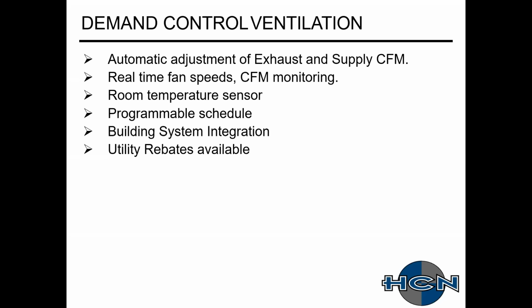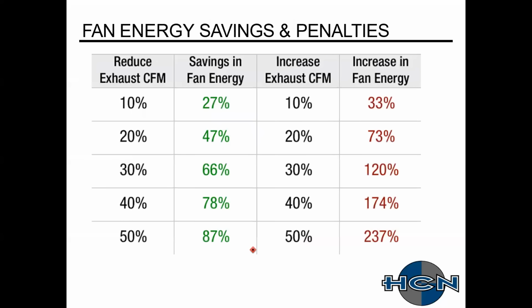Great, thank you. Mm-hmm. So your typical system for demand control, you're looking to automatically adjust that exhaust and supply based on what's happening real-time cooking. So you have, depending on what kind of system, temp sensors, optic sensors, there's building system integration. Depending on where you're at in the US, a lot of utilities are actually giving rebates because these systems are running off of VFDs. Fan laws, physics tells you, hey, this is what's going to be. So the biggest thing here is when you're reducing that CFM, you're saving fan energy. And typically what happens when most people are like, my hood's not working, let me just increase the CFM. You're increasing that fan energy, which is also increasing your horsepower typically. So the solution always isn't, hey, let's just crank up the hood and maybe everything will work fine.